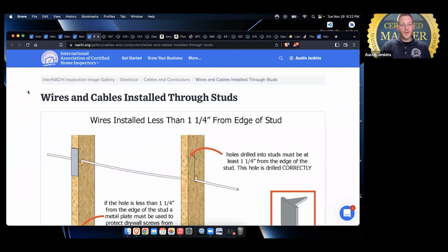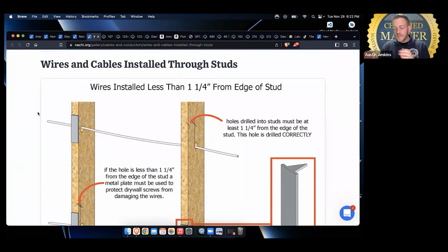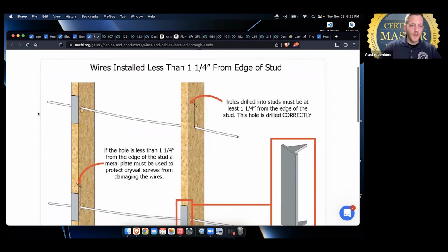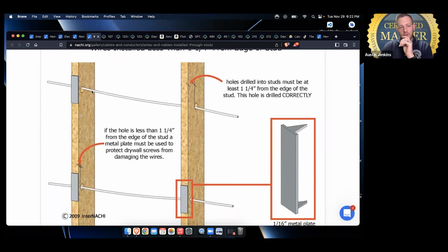Okay. So next, let's go to some things I look for whenever I do an inspection on a house that's either had some renovations or is new construction, a pre-drywall inspection. Most often, electricians are going to bore holes through the studs within 1.25 inches of the edge of the stud. And they're human, I get it. Sometimes it's a little bit shorter, a little bit longer. So if the hole is less than 1.25 inches from the edge of the stud, you need to have a metal plate. Essentially, when the drywallers put a sheet of drywall up and attach it with a drywall screw, once that sheet of sheetrock is on the studs, they can't see where the wire is. And usually drywall screws are not going to penetrate a metal plate or go further than 1.25 inches, as long as the wire is buried in the middle of the stud in most instances.